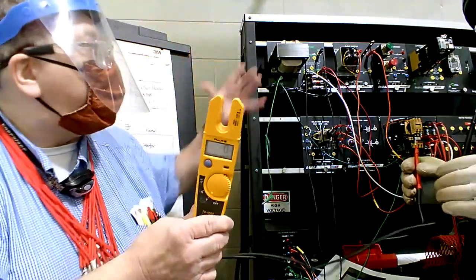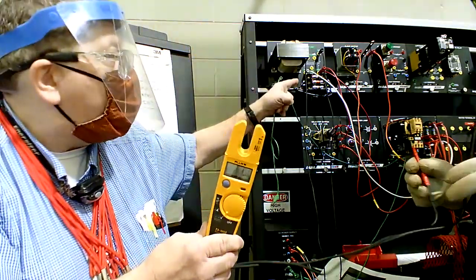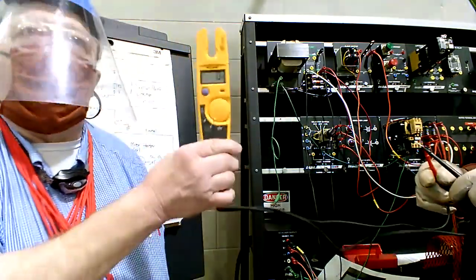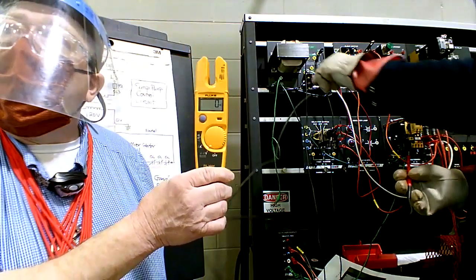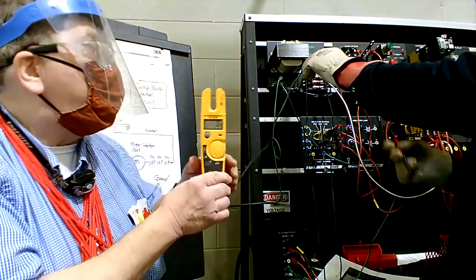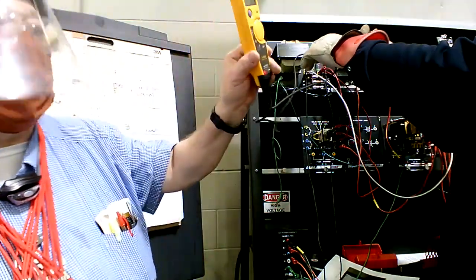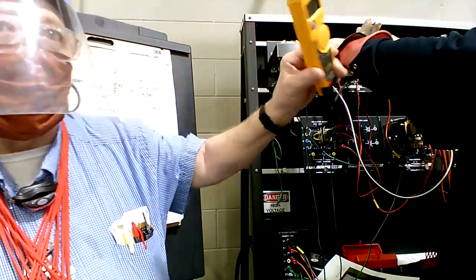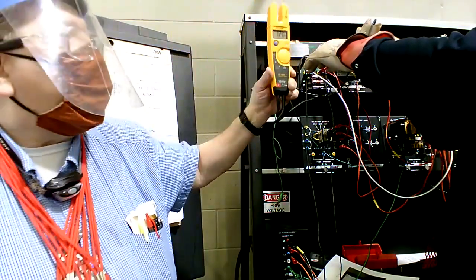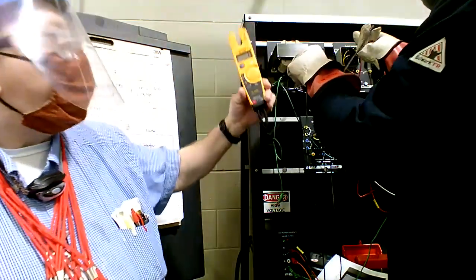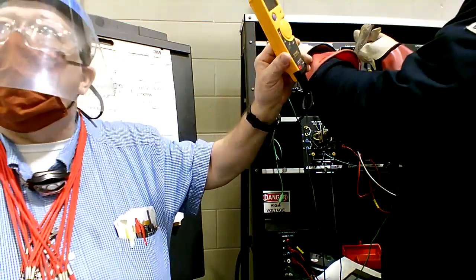So what do you do if you have a floating, ungrounded secondary like this? How do you properly measure it? You have to go to neutral, and then you read the 120 properly. And one more time, go from the float to some other grounded point. Yeah, 30 volts. You get a bad, erroneous reading.